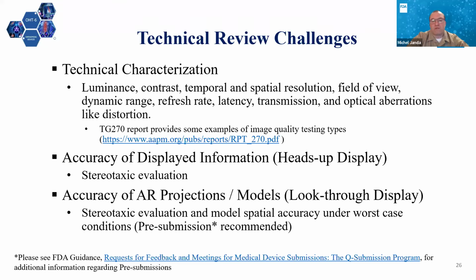They are also potentially subject to environmental factors such as HMD motion and background conditions. Therefore, an objective validation requires observation from an independent exterior method that has the same perspective as the user and includes anticipated environmental conditions. We highly recommend that you consider utilizing the pre-submission program to obtain FDA feedback to your performance testing protocols and methods.